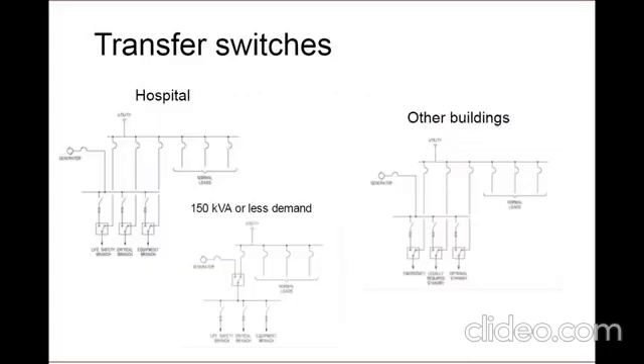Here we show three example single-line diagrams, just to give you an idea. The two on the left represent possible configurations allowed for a hospital installation. The one on the right represents an installation in a non-healthcare type building. Note that when branches of the essential electrical system are combined under one ATS, the downstream distribution is still segregated into separate systems following the wiring requirements in Article 517.